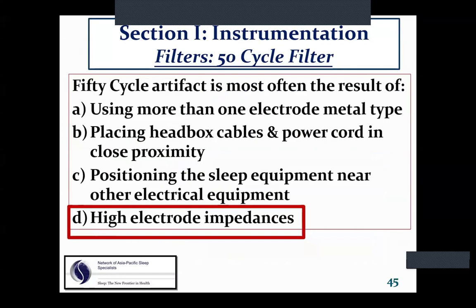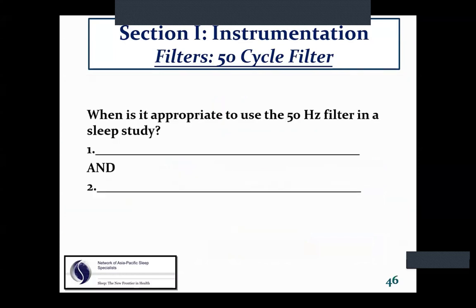50 cycle artifact is most often the result of high electrode impedances. So it's appropriate to use the 50 hertz filter in a sleep study, number 1, when it's in all channels. Number 2, after you've changed the system reference, if you have it on your system, and the ground. If it's only in select channels, it's most likely an impedance problem with either electrode in that pair.